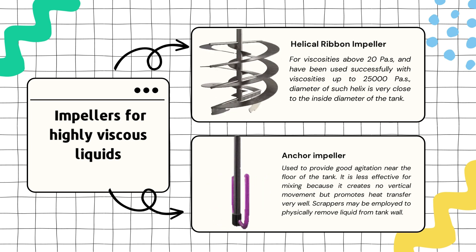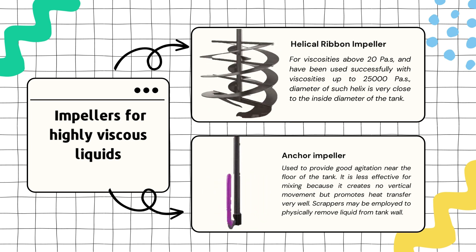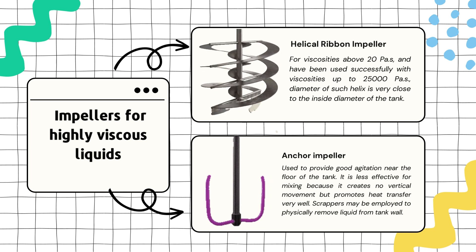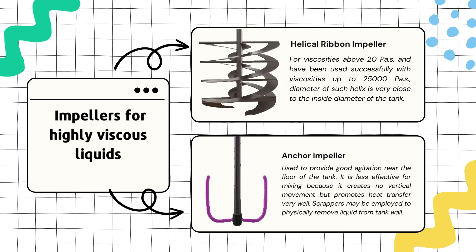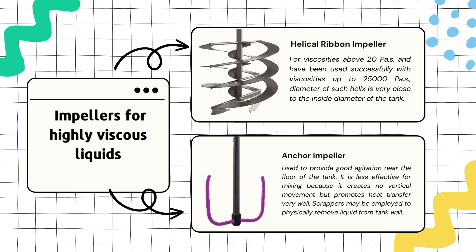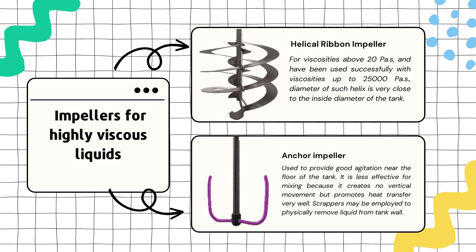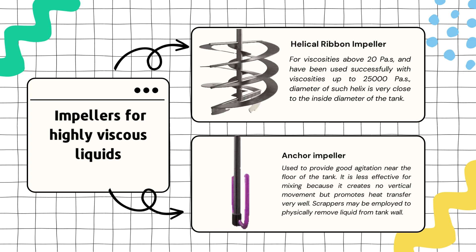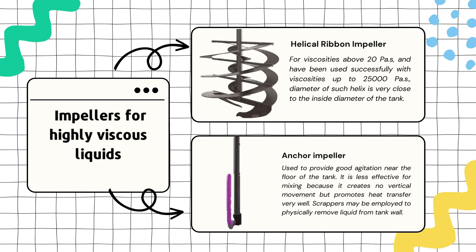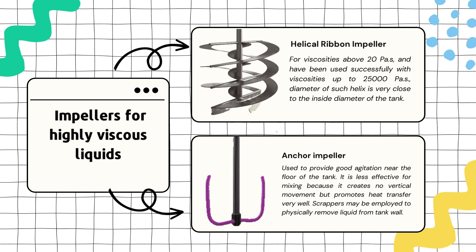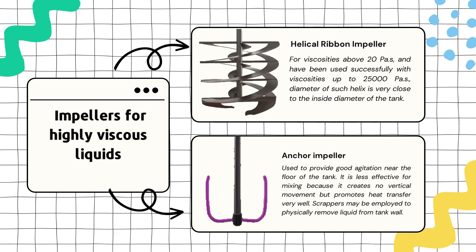The next type of impeller used for high viscous liquids is the anchor impeller. Anchor impellers are designed to provide good agitation near the bottom of the tank. They don't create much vertical movement but are excellent at promoting heat transfer. Sometimes scrapers are added to physically remove the liquid from the tank's wall.